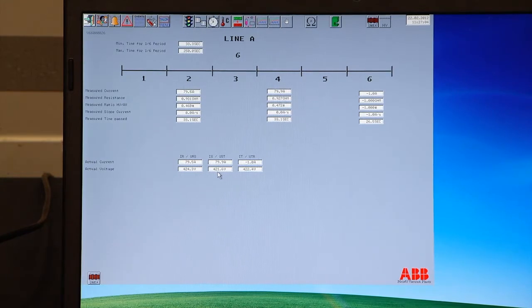Okay. So the whole high voltage measurement is to saturate the core to make sure there is no transformer performance anymore. So at 1 hertz, you would not saturate it. What do you set your hertz at here? Now we're running at 5 millihertz.